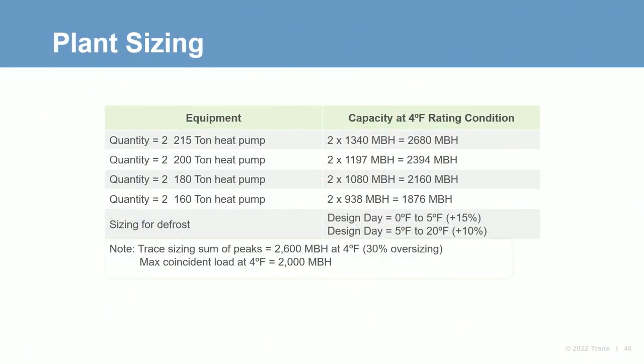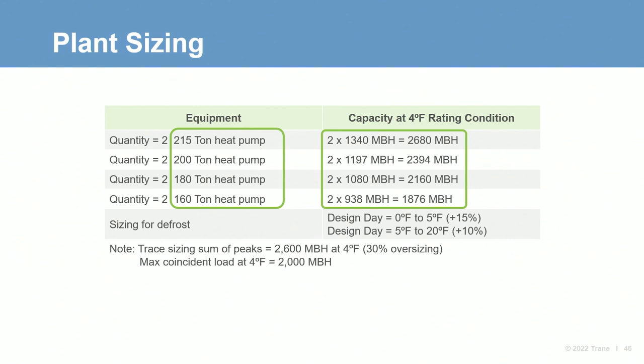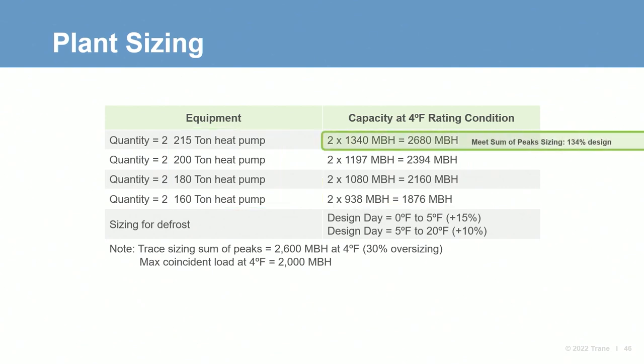Now that we understand how air-to-water heat pump equipment will respond to both outdoor air temperature and defrost, we can start to size our plant. For our K-12 school, the sum of peak loads is 2,600 MBH, and the block load is 2,000 MBH. The equipment list shown here provides four different nominal heat pump sizes, along with the heating output at minimum ambient. If sized based on sum of peaks, we'd end up oversizing the plant by at least 34% from the design.